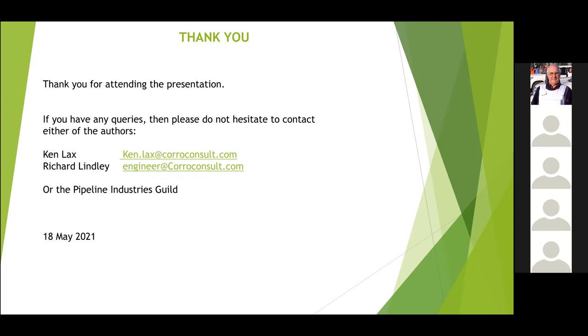Another question: in a polyethylene pipeline, would this principle apply to any metallic components such as valves or metallic joint sets? Highly unlikely, because it's not going to be an attractive path home for the current. So if you've got a metallic valve in a plastic pipe, it's not likely to be affected by stray current. It might be affected by induced voltages from AC if you're at the extreme end of the high-voltage range of the AC overhead cables, but unlikely.